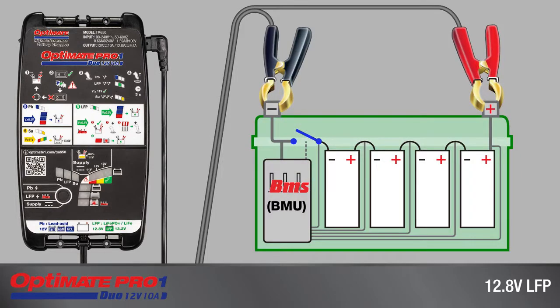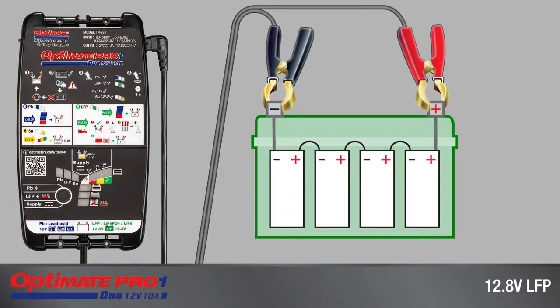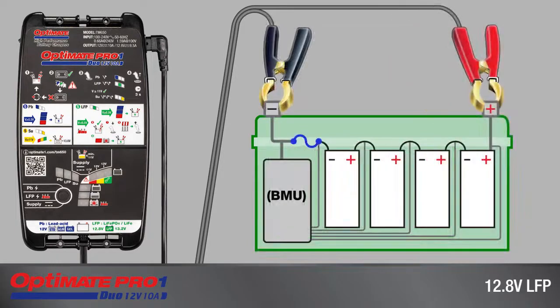This charger can reset new LFP batteries delivered in sleep mode or recover deep discharge batteries. It also charges and tests LFP lithium batteries with different types of battery management systems, including standard batteries with basic cell balancing, BMS batteries with a non-resettable fuse that protects against severe overvoltage and short circuit, or advanced BMS batteries with resettable protection against deep discharge, overvoltage, and short circuit.